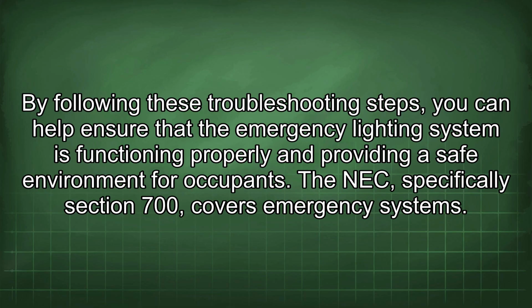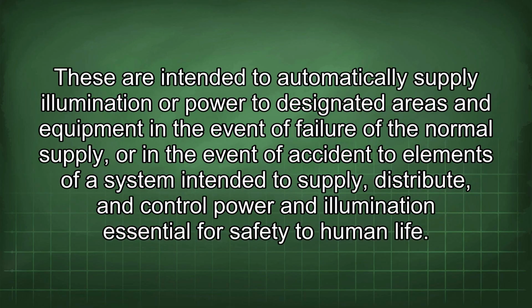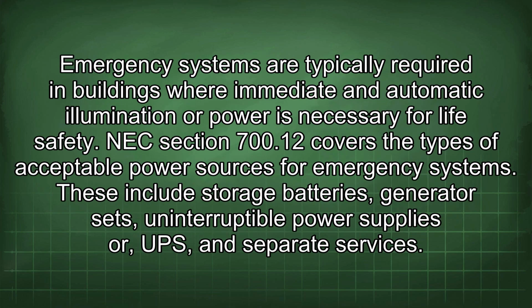The NEC, specifically Section 700, covers emergency systems. These are intended to automatically supply illumination or power to designated areas and equipment in the event of failure of the normal supply, or in the event of accident to elements of a system intended to supply, distribute, and control power and illumination essential for safety to human life. Emergency systems are typically required in buildings where immediate and automatic illumination or power is necessary for life safety.